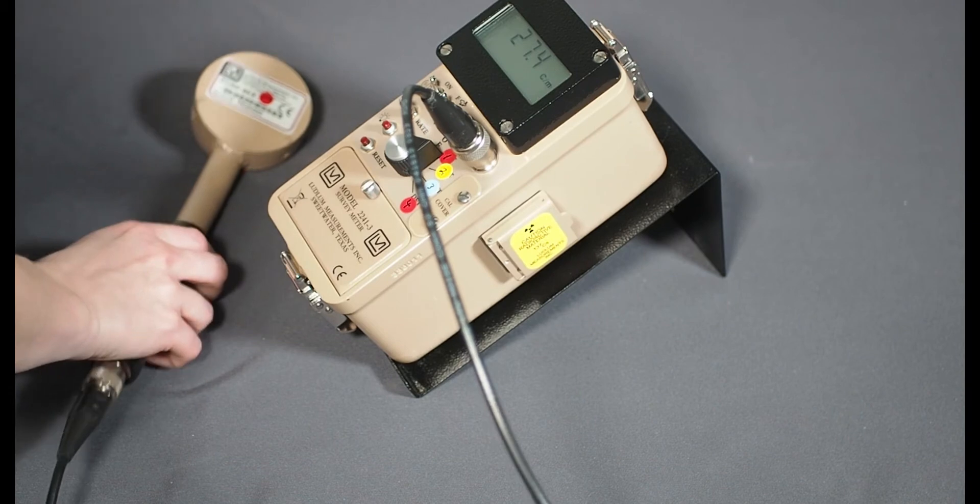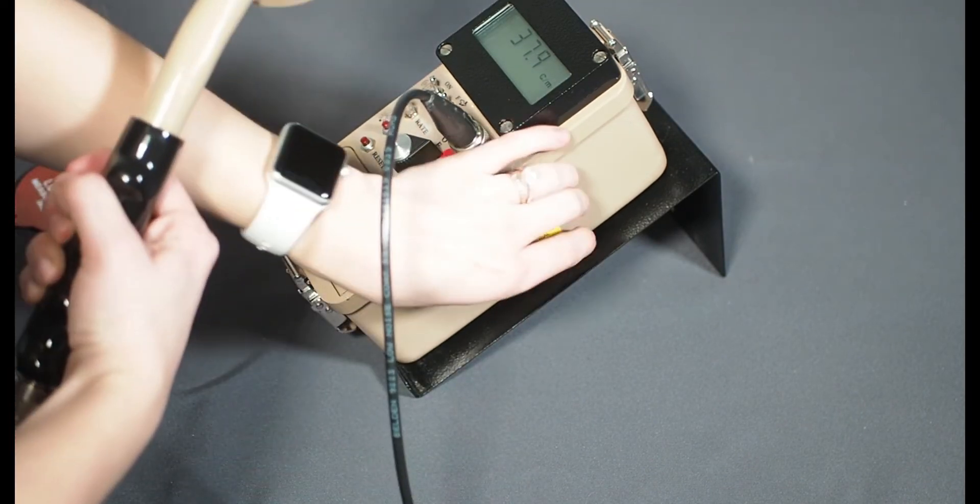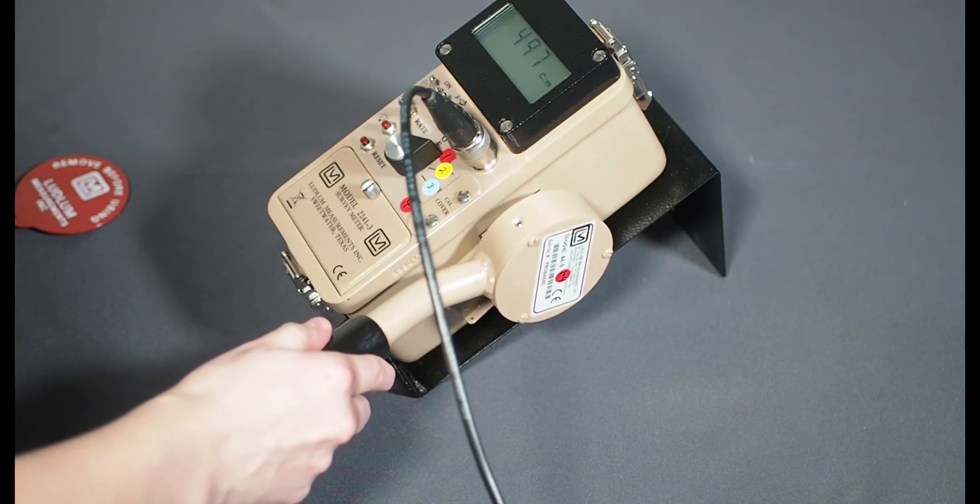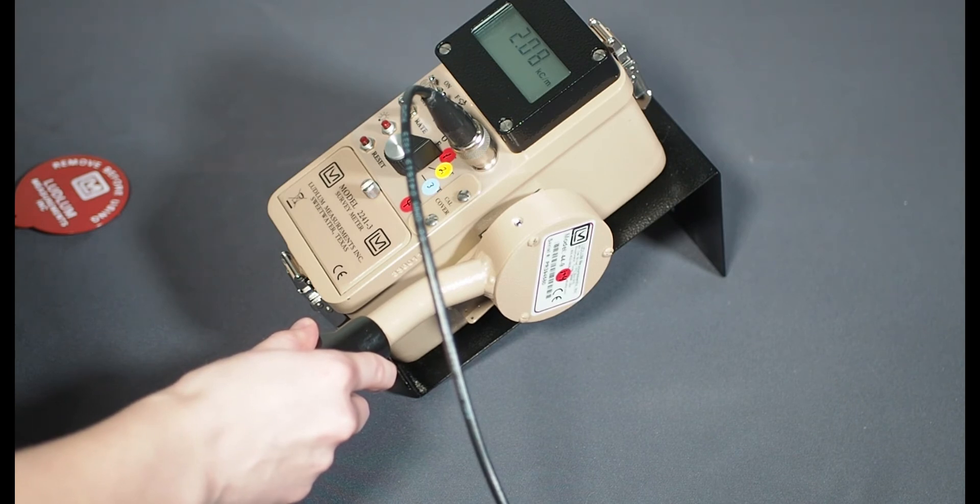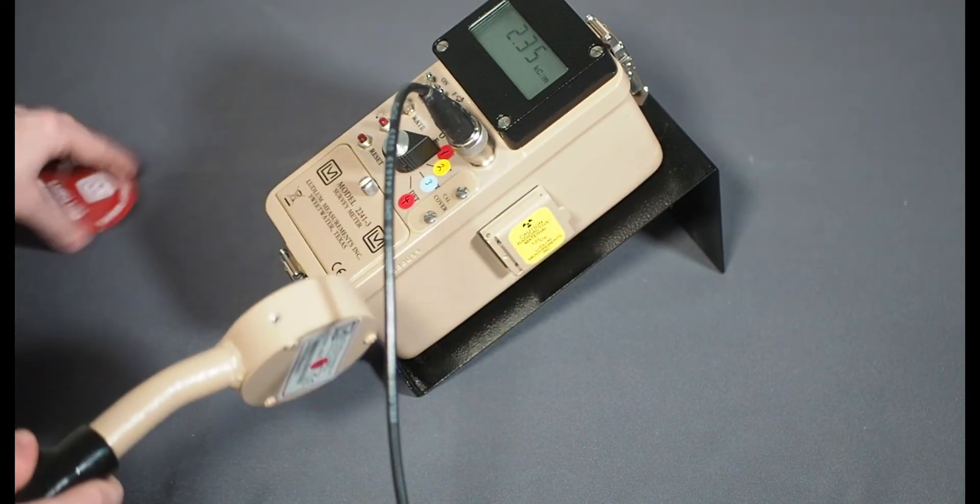Perform the check source test by opening the check source cover door and placing the face of the 44-9 against the check source. Compare the reading to the reference reading listed on the calibration sticker on the side of the meter. If the reading is within plus or minus 20%, then it passed the test and the instrument is ready to use. If not, the detector should be taken out of service.